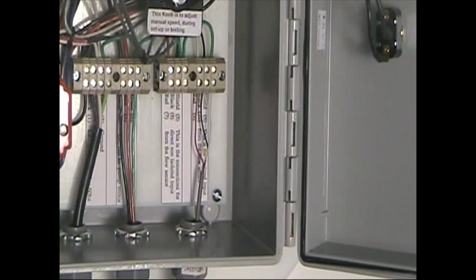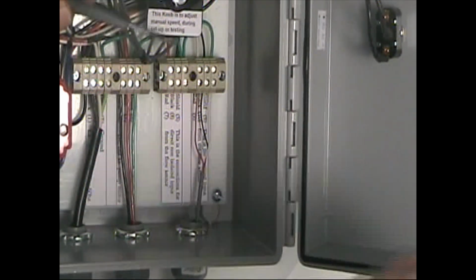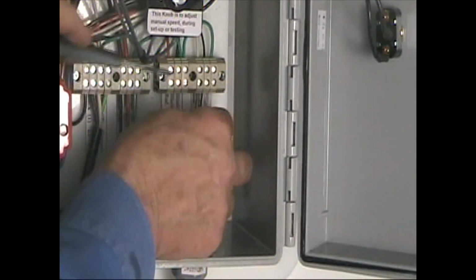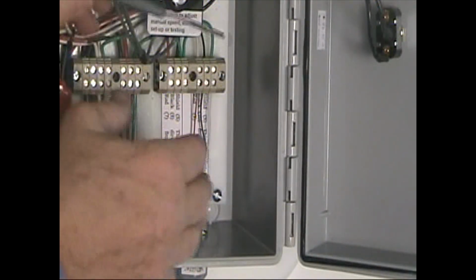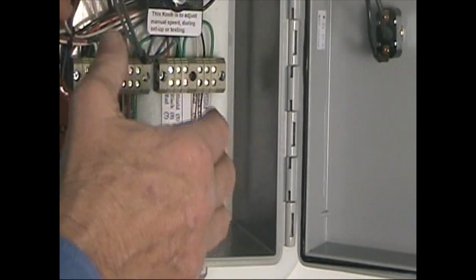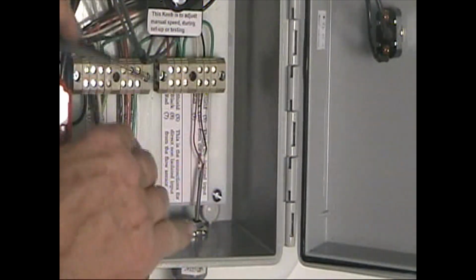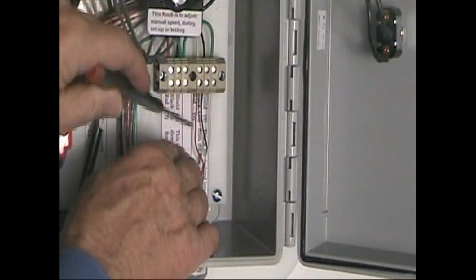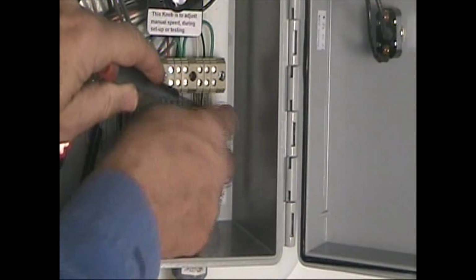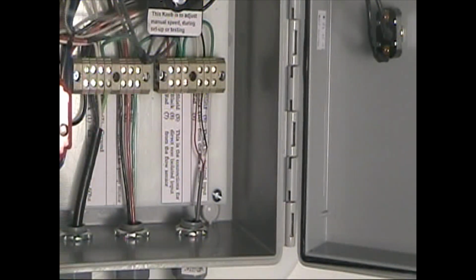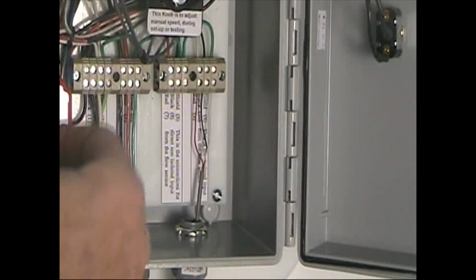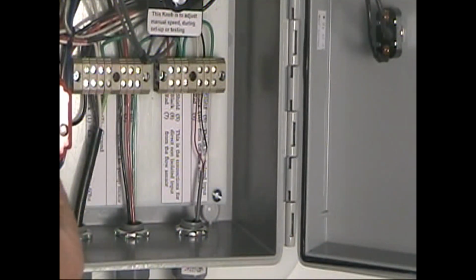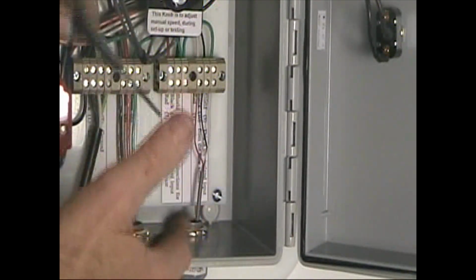The next thing you're going to do is connect your flow sensor connections, and you'll have a conduit that will run from the controller to your flow sensor, and it'll have a cable. Each flow sensor is different, so consult your manual and drawings for that. But you normally would do, like for that industrial one, red to red, black to black, and your white would be the shield, which would go to your sensor. The different mass meters or other meters are different, so consult that. But that's basically what you do.